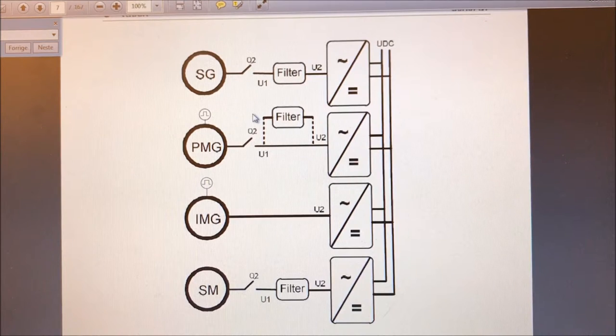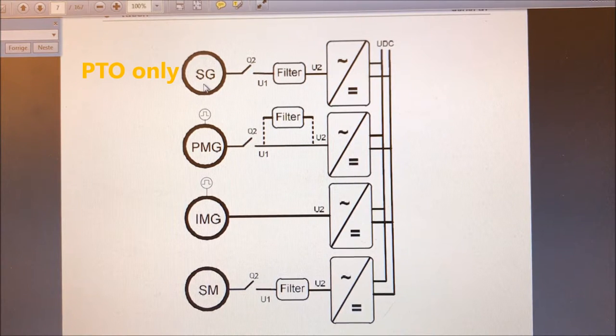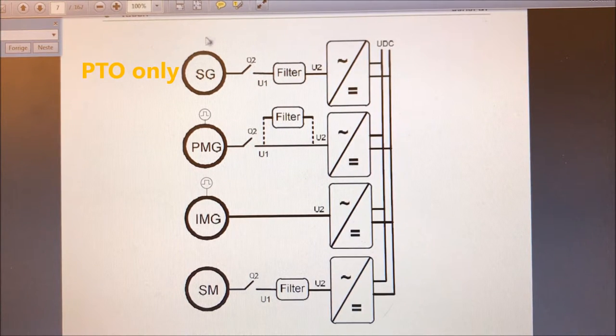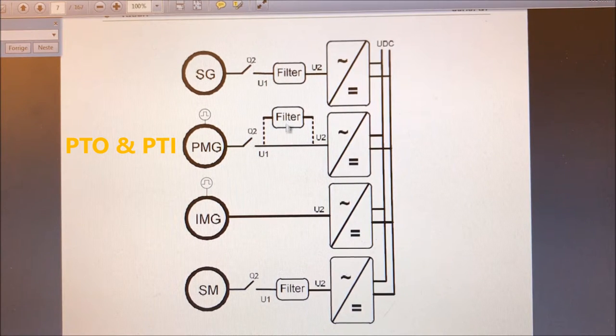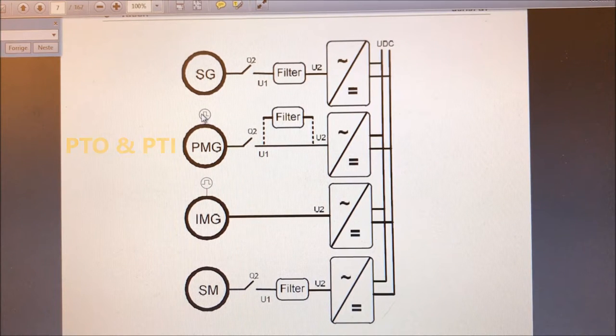If we look into the manual for the generator application, we will find the different motor and generator types that can be utilized. Synchronous generators here with a filter — typically an LCL or LC filter — and the configuration will be very similar to active front end functionality. Then you have a permanent magnet generator, which you can use with or without a filter. Note that you should use a speed encoder, typically an incremental encoder at 1024 pulses per round.